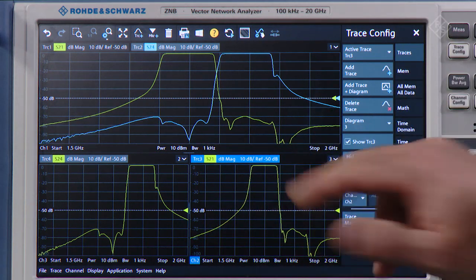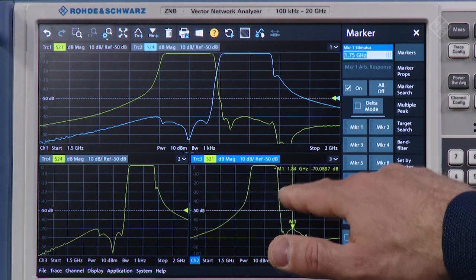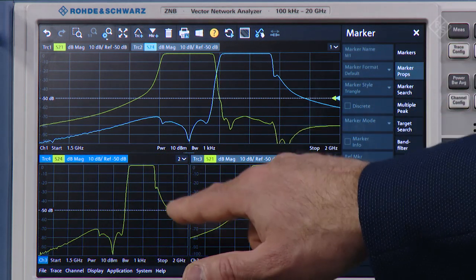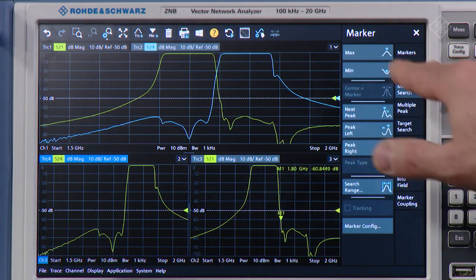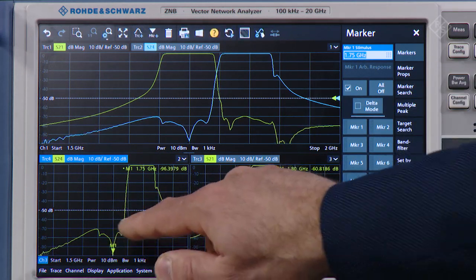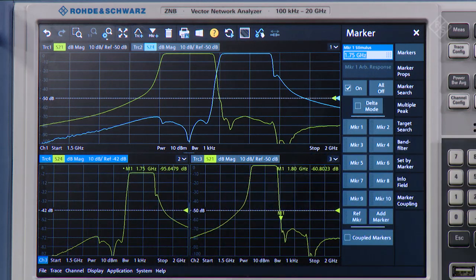Let's add some markers. These markers will help us later set up a segmented sweep. The segmented sweep will help us optimize the measurement setup for the band reject region. I will select the low band and add a marker, dragging it to where I want it to be. Then I will select the high band region and add a marker there as well, dragging it to the desired position. If you cannot do it by finger, just use the knob.